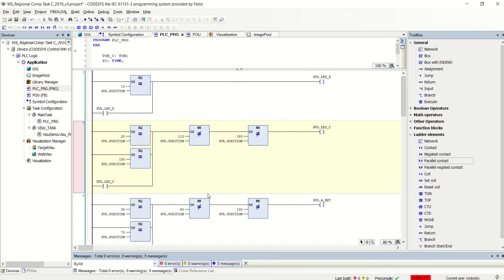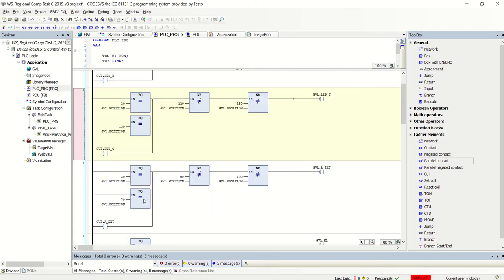So now we look at these. This is something that I want to show you, when we're getting two going out at the same time. Okay, so at step 140, A should go out and B should go out. So two things happen at the same time, step 140. Well, let's look at A first.